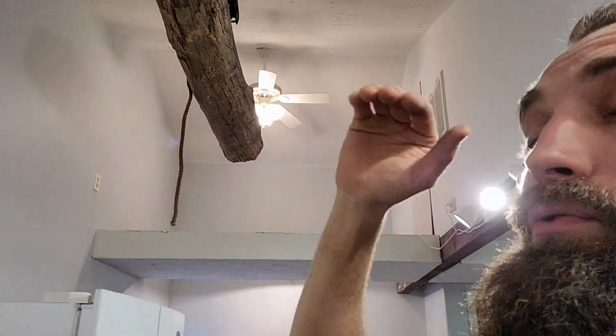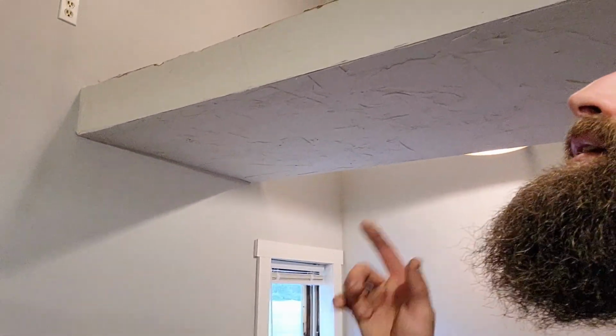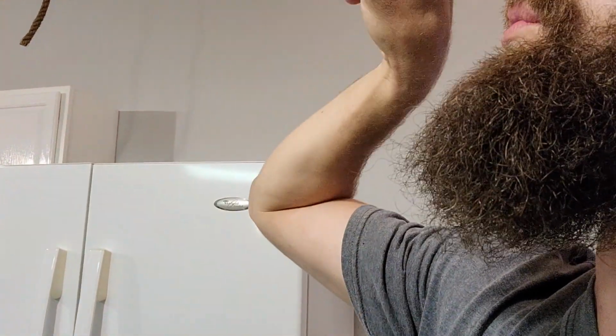It's obviously unoperational at this point, but what we need to know is we've got all this additional volume in our kitchen and our dining area that we have to contend with. This is all air that needs heated and cooled, and we need to circulate this air through our building as well. You will see that at one point they had a return stabbed in up on the right-hand side, pulling air from that area.